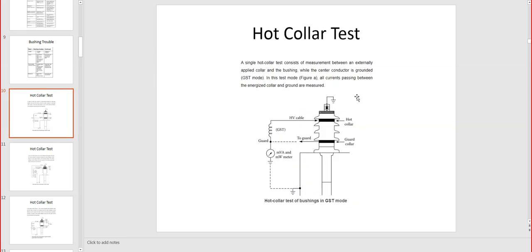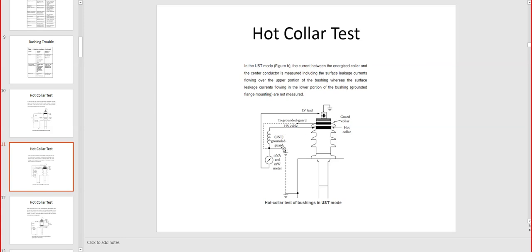Next slide is actually looking at the hot collar test. So here is the way we apply the hot collar test. The measurements can be done in different configurations. We can apply the hot collar connected to a millivolt, amps, milliwatt meter, and we're going to measure the actual discharge from the tap to the ground. So that is the GST mode connection. Then you have UST, a different connection with a ground connected in another way. Pretty much it is measuring the same, the capacitance and the leakage current, the leakage power that goes through the bushing from the hot collar to the ground. In this case, we actually grounded the top. If you see the top of the connection where normally the cable comes into the bushing, it is also grounded.